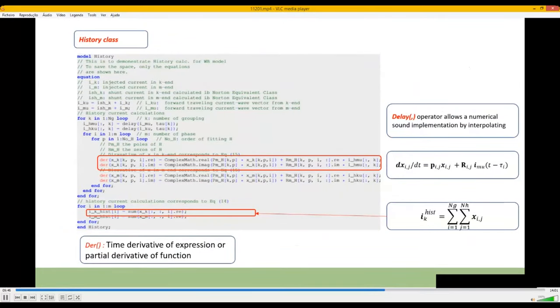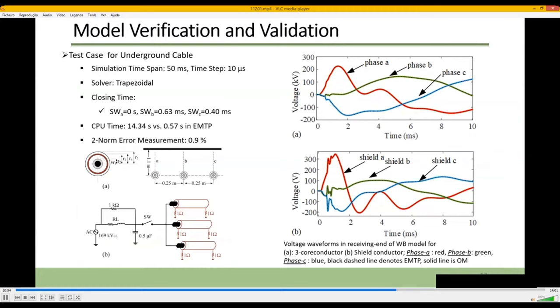This slide shows the calculation of history terms. We can see the procedure for calculating the history terms of the wideband model. Here we can see how the derivative and delay operators make modeling easier. Now we can check and validate our models with EMTP. In this case, the study of a six-conductor three-phase cable has been simulated, with data from EMTP examples. Each pole of the switch is closed at a specific time. The voltage curves for conductors and shields at the receiving end of the cable are found here. The Modelica curves stick to EMTP bounds exactly. The CPU time and relative error norm are noted here.